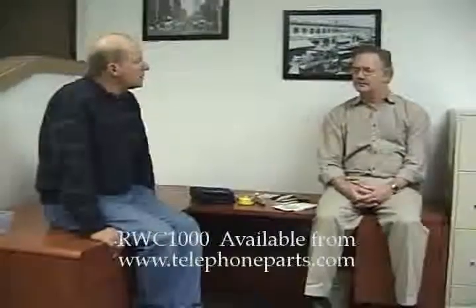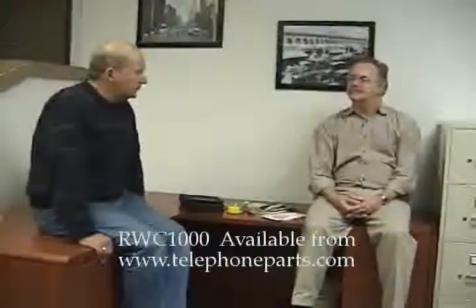Now, before, the cable installer would have to spend a lot of time. Before he had the Real World Certifier, he would have to go in and install a parallel cable, or what they call a sister cable, and then plug that into the same user equipment and then show the customer that, look, the parallel cable works the same as the original cable, therefore the original cable must have been good.